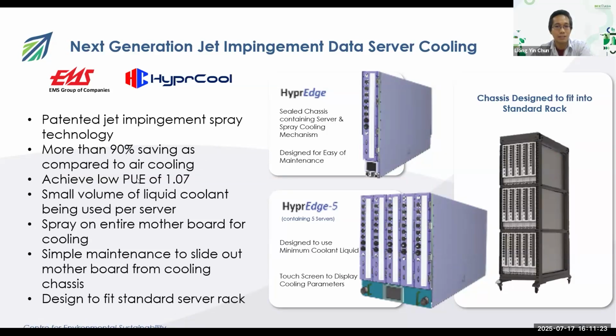In case you're not familiar, let me introduce PUE, the power usage effectiveness. For 1.07, it means that for 1 kilowatt of IT power for the server load, we only use 70 watts of energy for cooling. The current standard advised by IMDA is 1.3, meaning for 1 kilowatt of IT load, you use 300 watts to cool it down. But now we use just 70 watts, and as I mentioned, we've managed to reduce it further to 40 watts of energy to cool down.